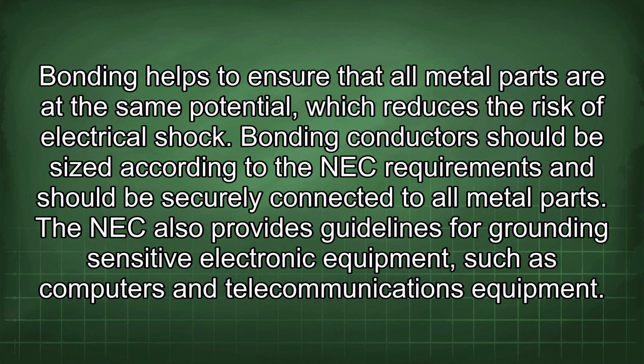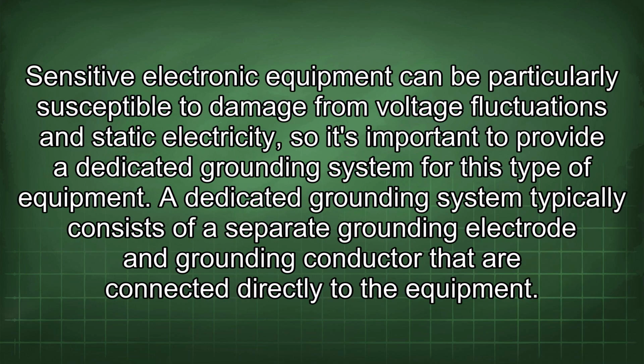Bonding conductors should be sized according to the NEC requirements and should be securely connected to all metal parts. The NEC also provides guidelines for grounding sensitive electronic equipment such as computers and telecommunications equipment. Sensitive electronic equipment can be particularly susceptible to damage from voltage fluctuations and static electricity, so it's important to provide a dedicated grounding system for this type of equipment.